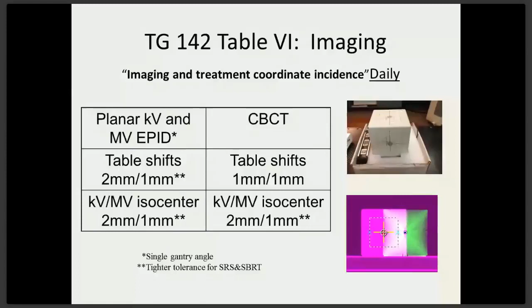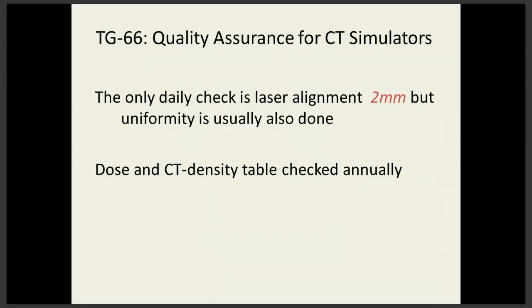CT simulators, not a lot to do on a monthly basis, a daily basis. Some departments require the therapist to run a uniformity test to make sure that the HU of water is consistent. Monthly, some physicists do a test of CT number for the different density plugs that are in a CT phantom. And those are acceptable tests for the CT simulators.